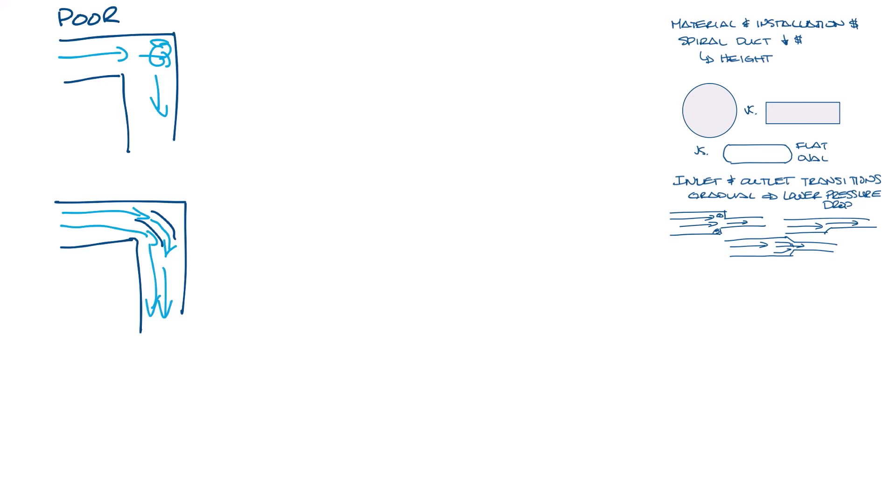That's why you see turning vanes in 90 degree bends sometimes. They guide the airflow around the corner and reduce turbulence, which reduces the pressure loss. But a nice, soft 90 degree bend would be ideal.